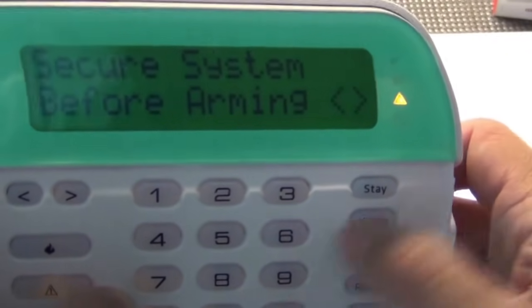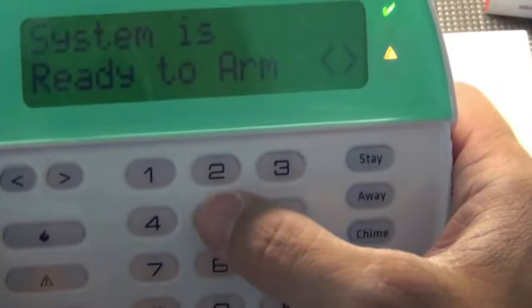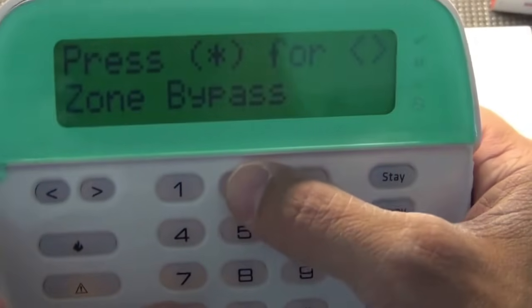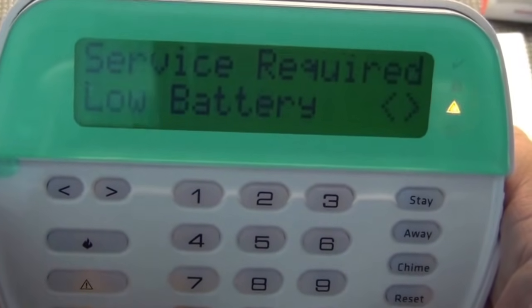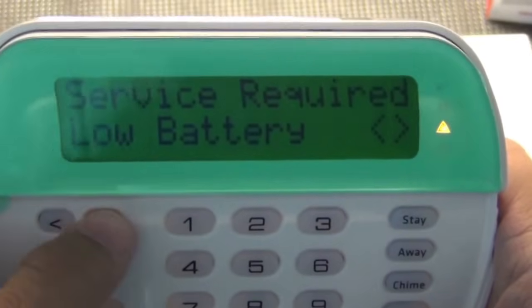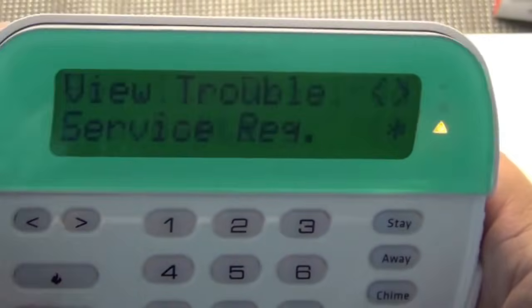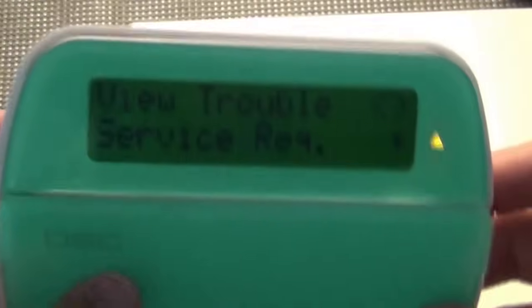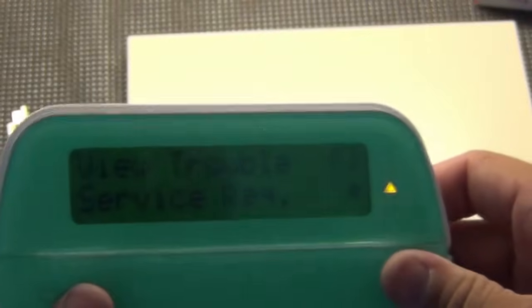I am going to hit pound, pound, pound to exit programming. I've got an orange triangle. I want to see what that is. It's probably going to say low battery and something about a siren. Service required. I'm going to hit star. It tells me low battery. If I scroll, I'm going to see bell circuit. That's just basically because right now I do not have a siren hooked up to the system and I do not have a backup battery hooked up to the system. If I hook those up, that trouble light will go off.